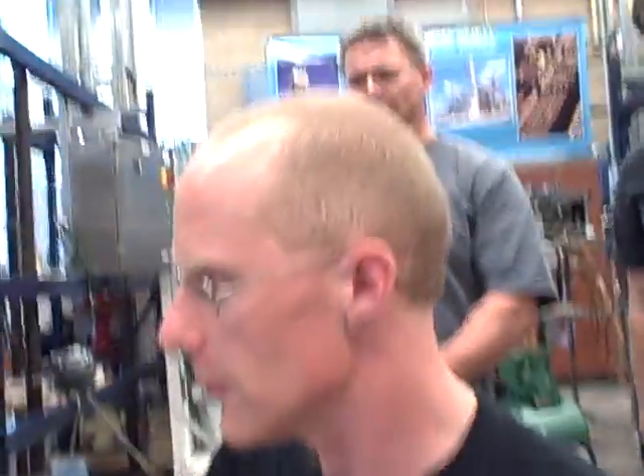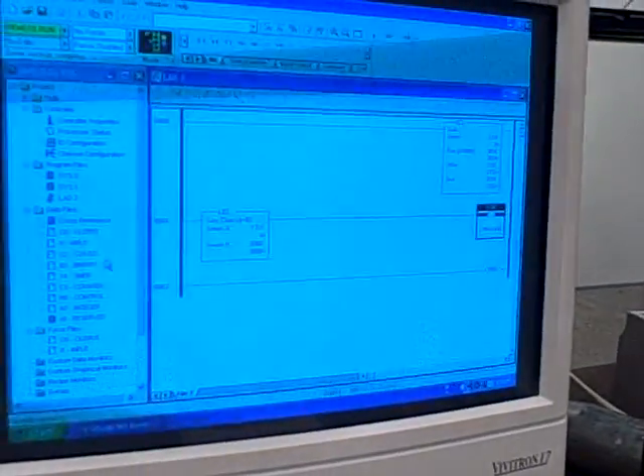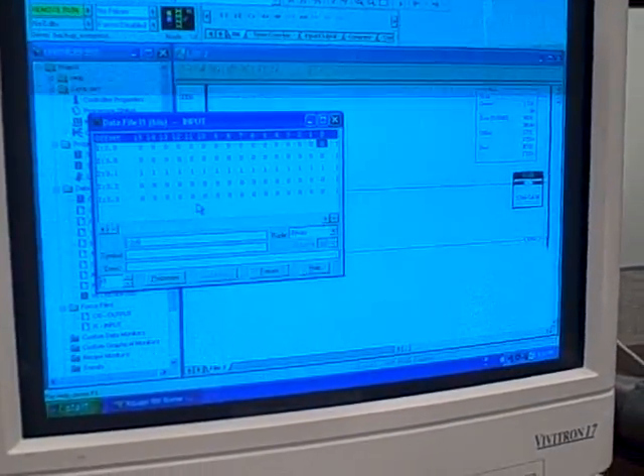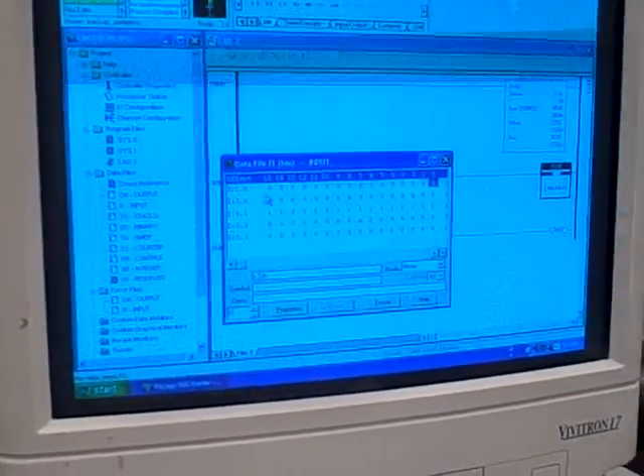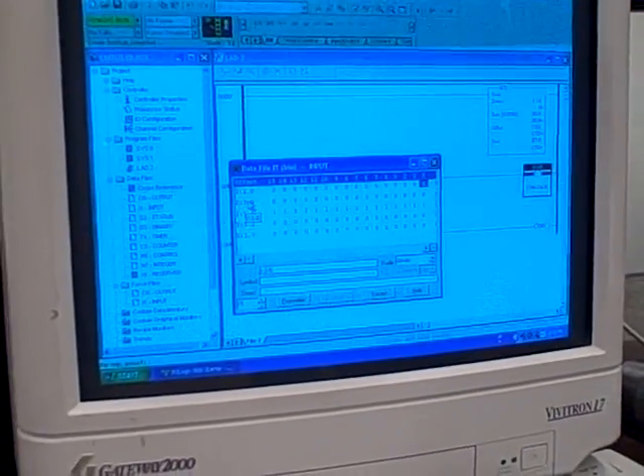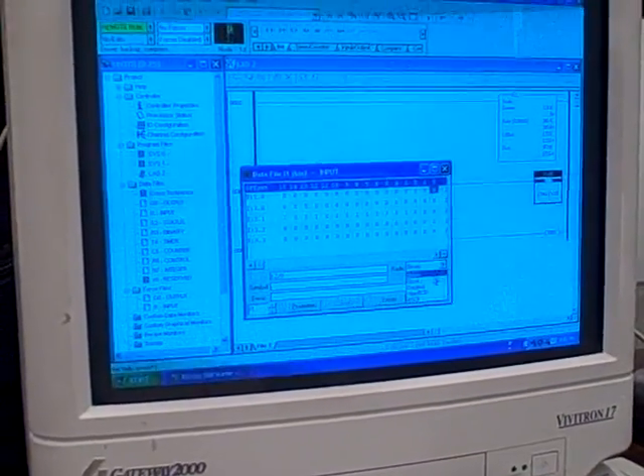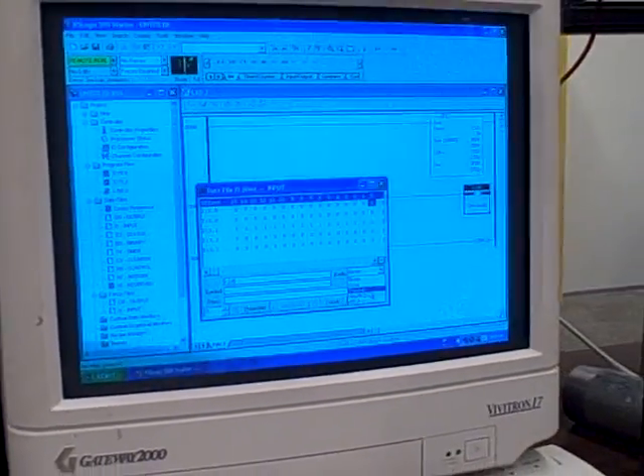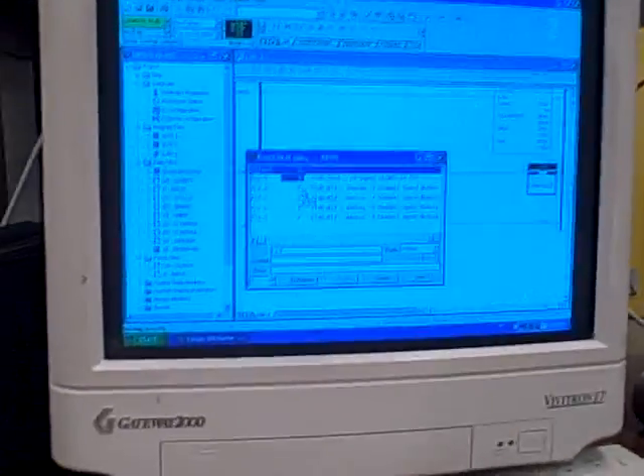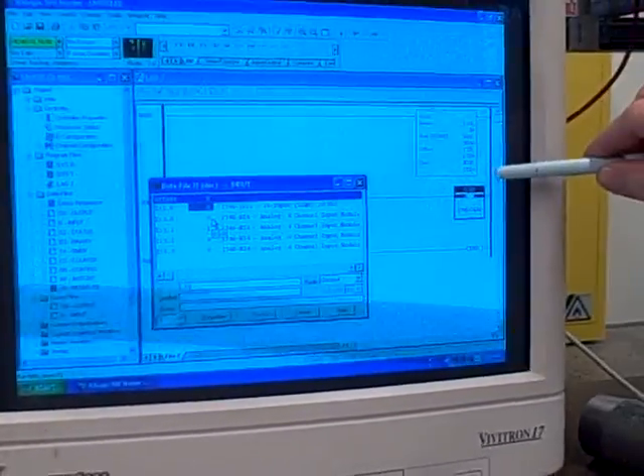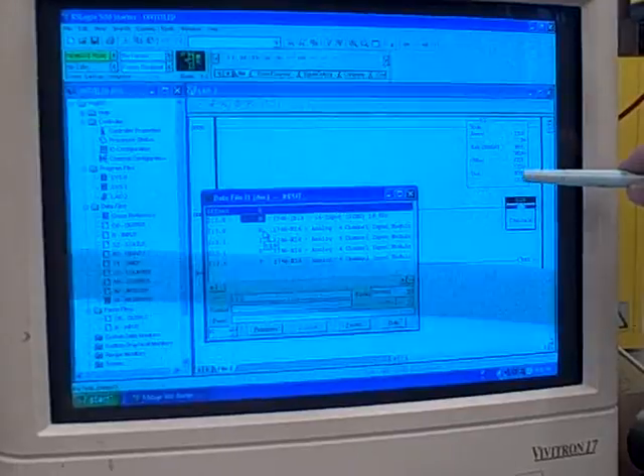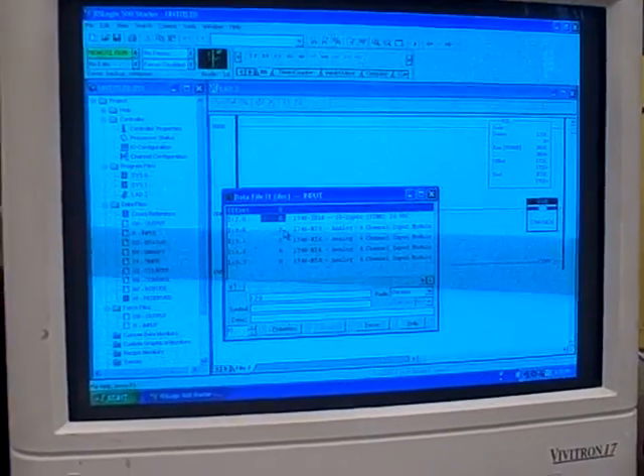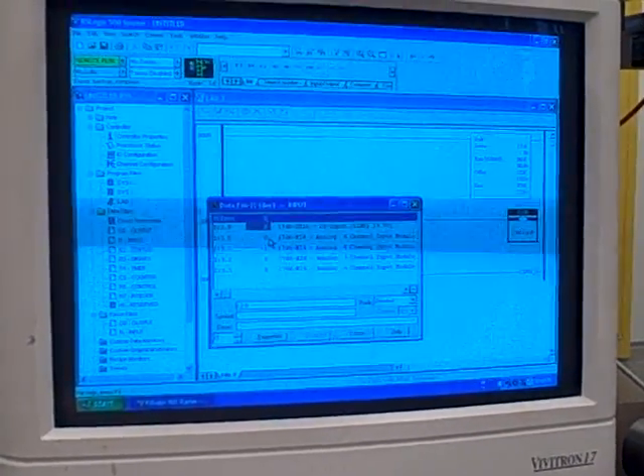We're looking now at a program where we're taking an analog signal on our Allen Bradley SLC 500 PLC. We're taking an analog signal in through input card 3 channel 1, card 3 word 1, this 16-bit word. We've already scaled it, so it's going to read out on a scale of 3,000 to 8,000, which is fixed-point notation for 30 degrees to 80 degrees.